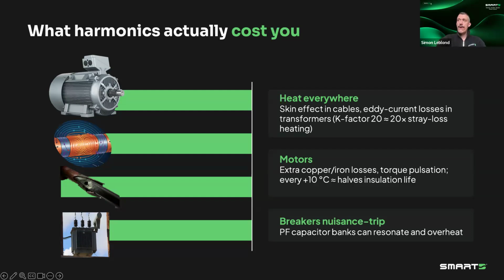It really affects any of the equipment in your system exposed to those harmonics. You do also have other impacts outside of heat. So you do have a nuisance impact, like breaker nuisance trips. You can have a capacitor bank, if present, resonate with the harmonic source and overheat. But generally, the main consequence, the one that you can always count on, is heat.